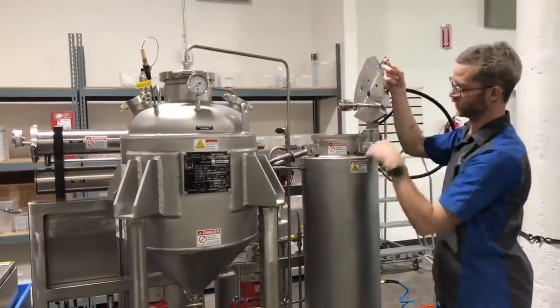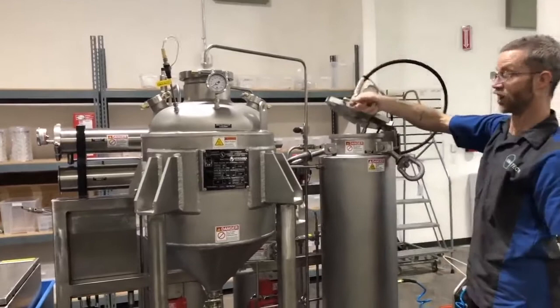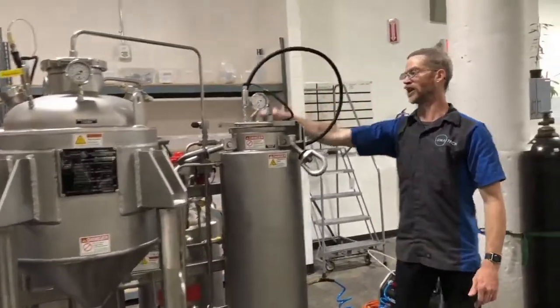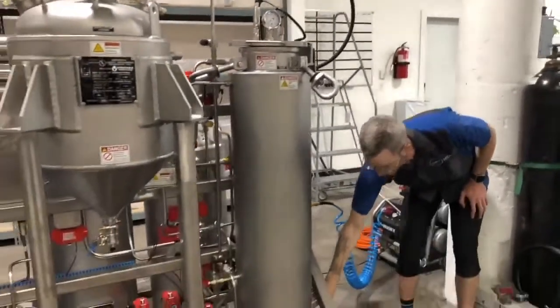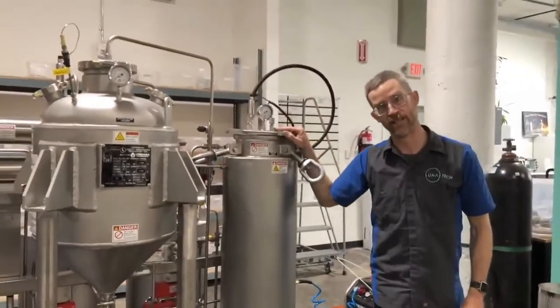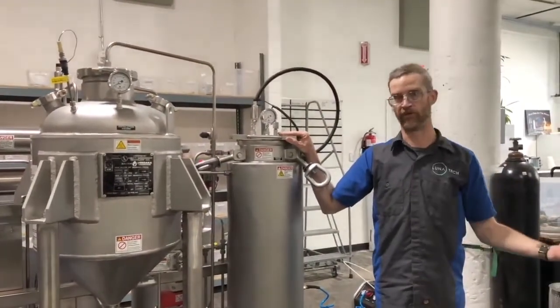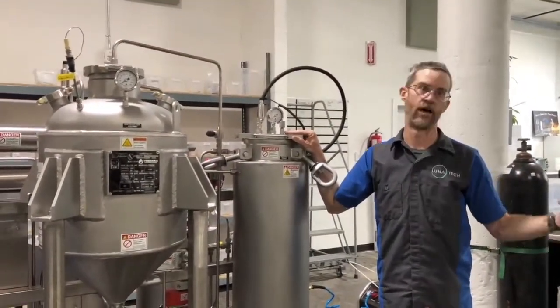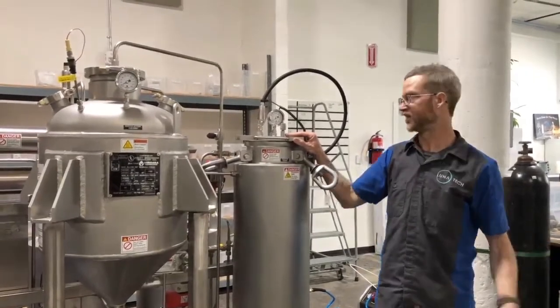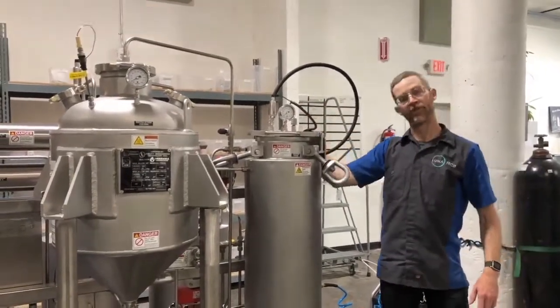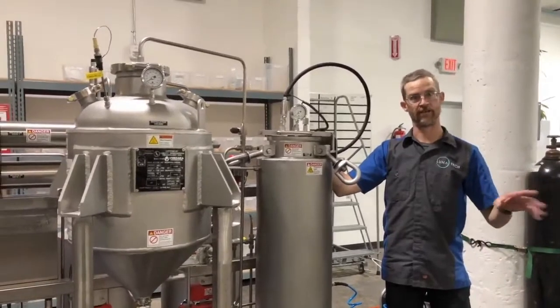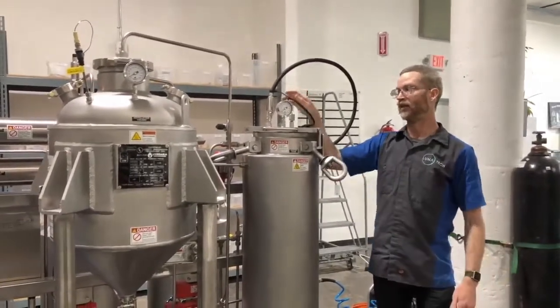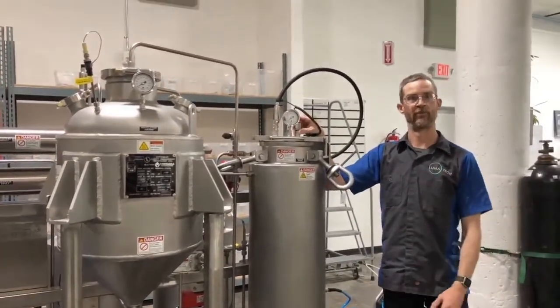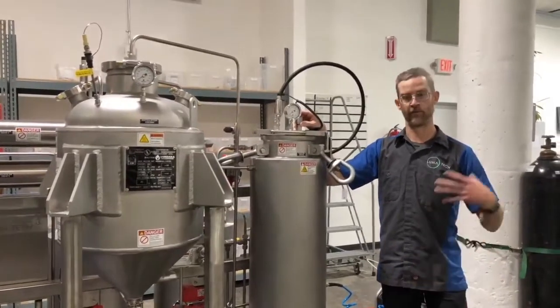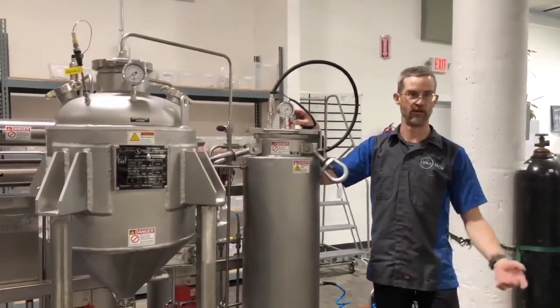We've got two sensors also in the reactor that are optical, one at the top and one at the bottom. The reason we have the redundant sensor at the top is to prevent overfilling of a hydrocarbon solvent - obviously that would be a bad circumstance. So if the optical sensor for some reason fails or does not read correctly, the float sensor will back that up, so we won't have to worry about overfilling butane or propane.